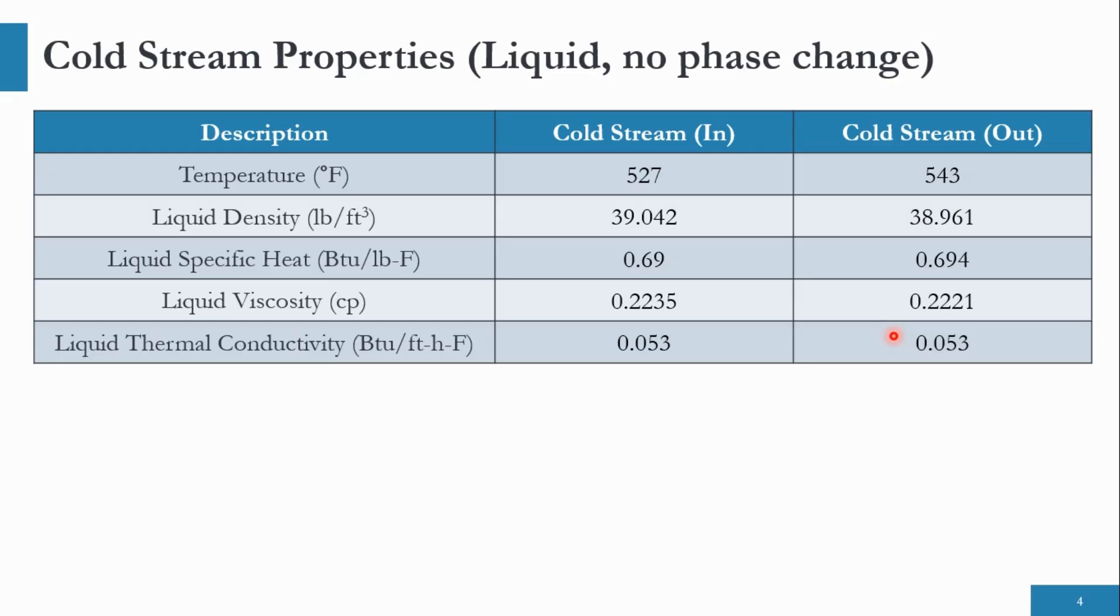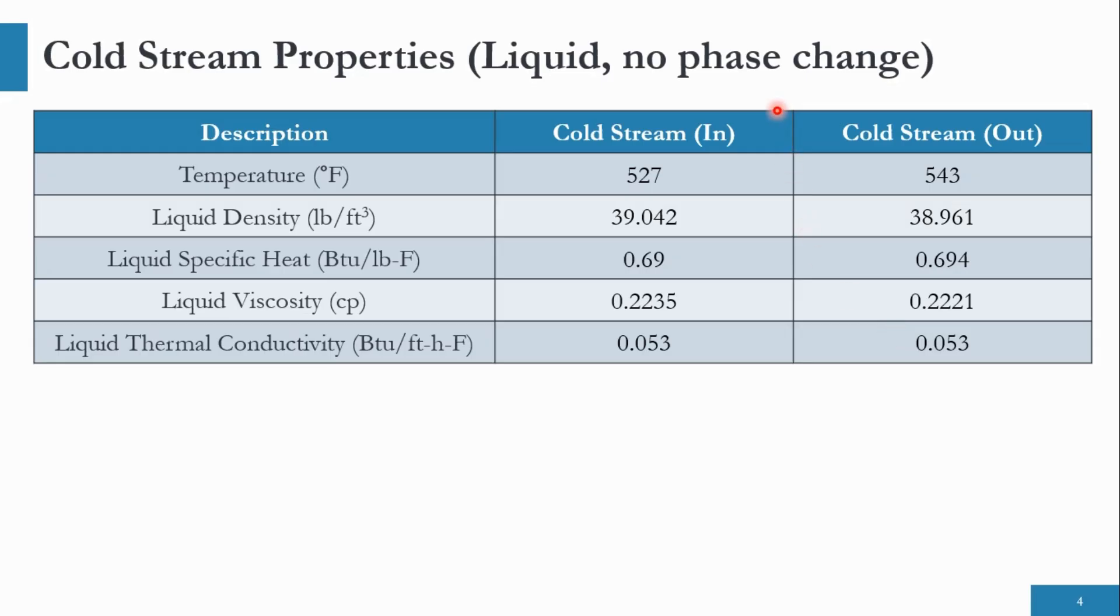So we will specify first the overall information means the hot stream inlet, outlet pressure, temperature, flow. Obviously one of the flow because the other flow will be calculated from the formula of Q1 equals Q2 and M1 CP1 DT1 equals M2 CP2 DT2. And then we will specify the properties and both these streams are in liquid phase with no phase change.